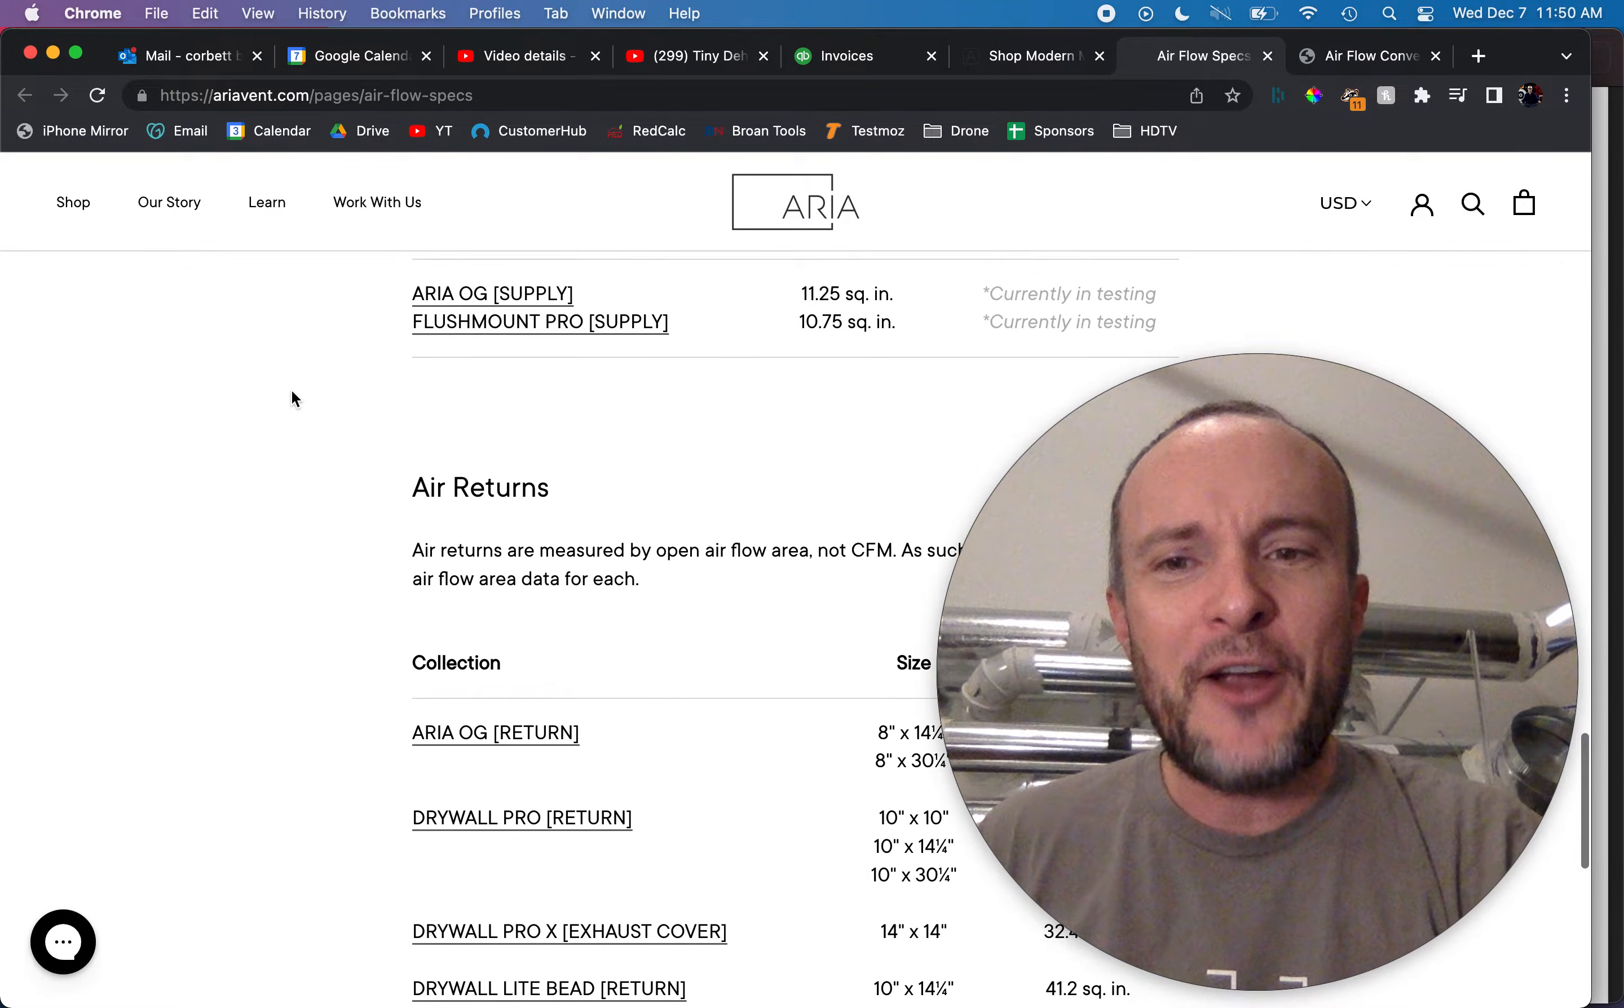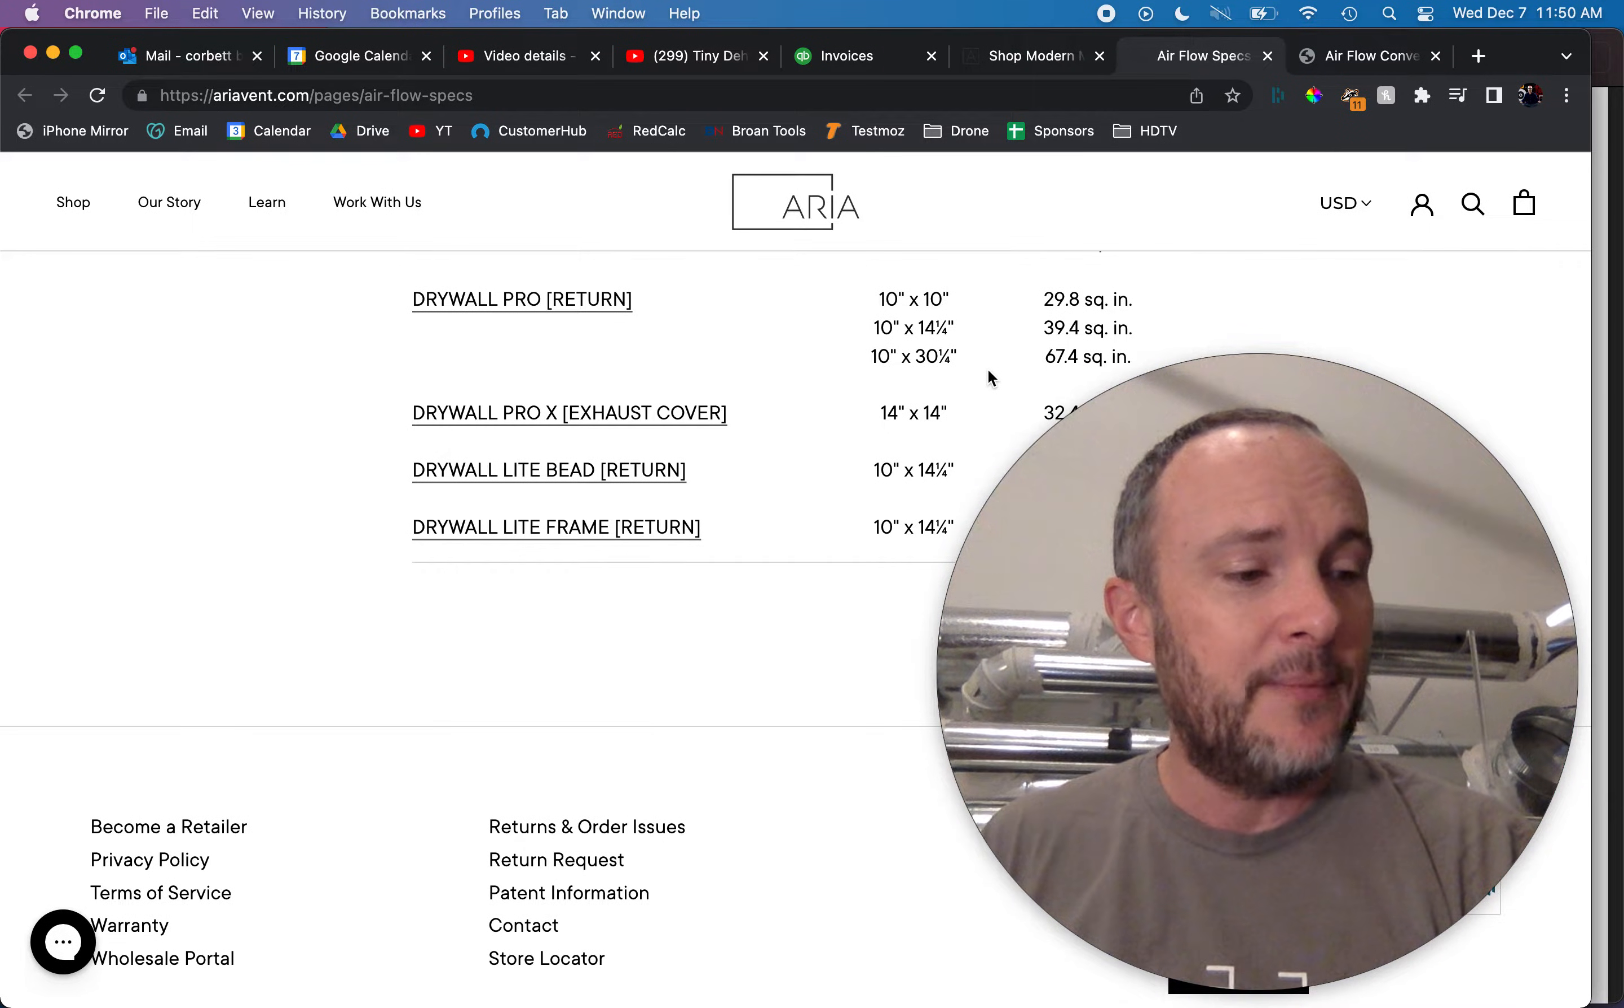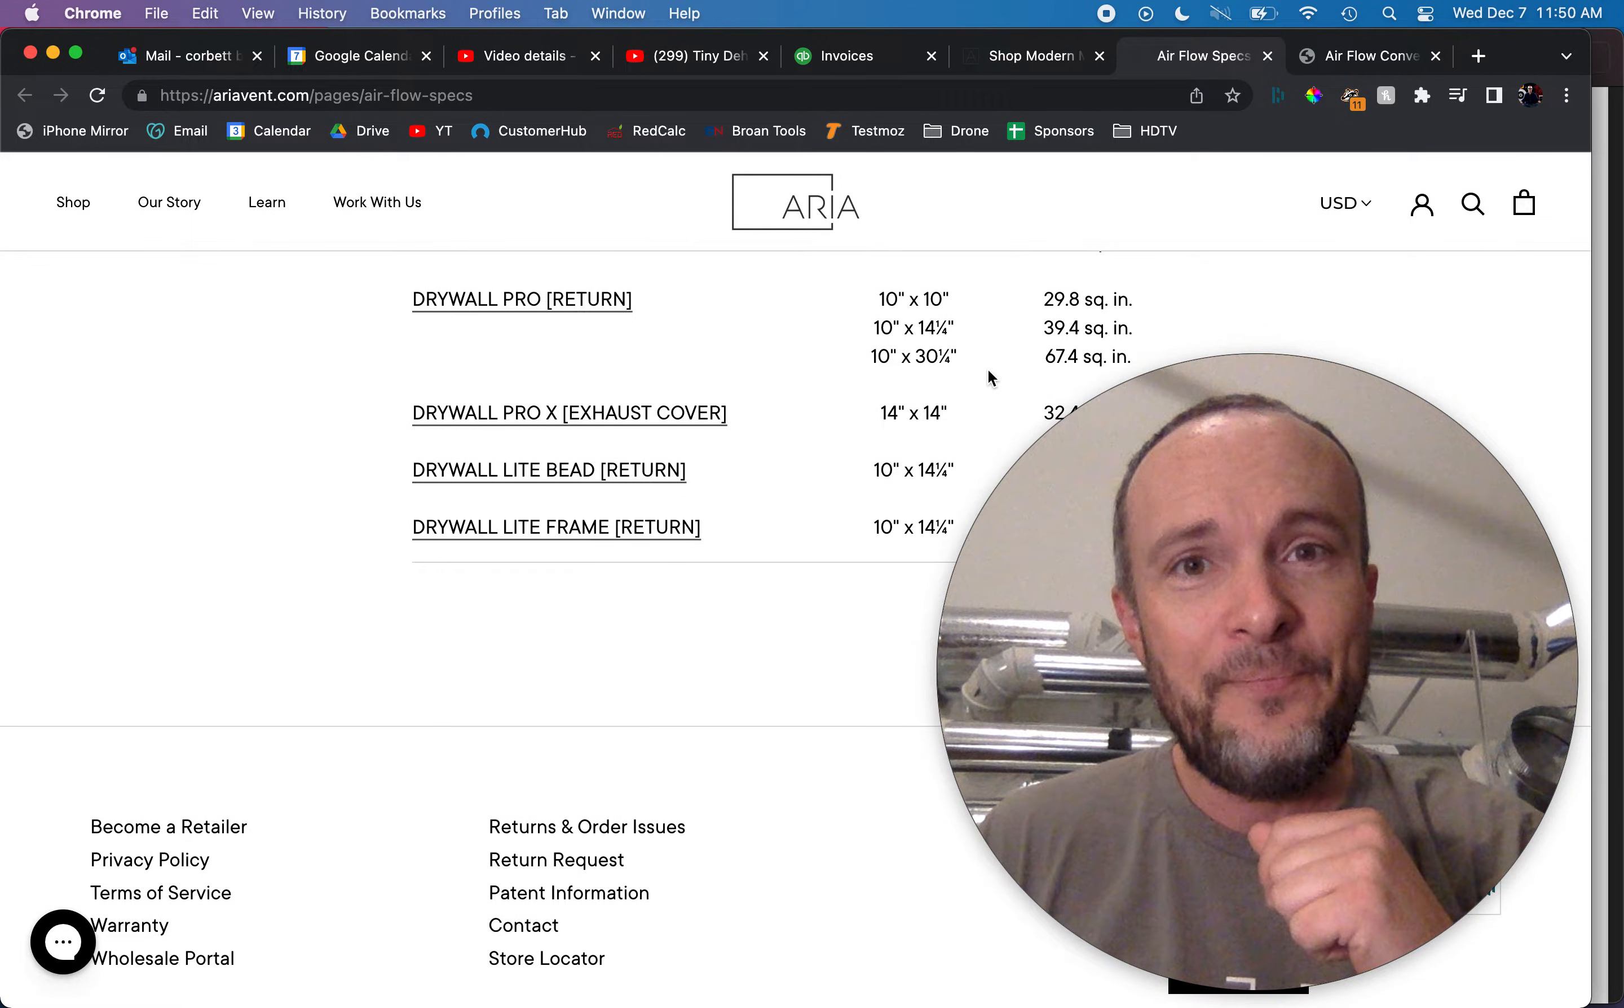The air returns which look exactly like this, it's just the perimeter, right? The entire inside of the thing is going to be filled. The biggest return they have is a 10 by 30 which gives you only 67.4 square inches. 10 by 30 is 300. So 67.4 divided by 300 is about 22% net free area.